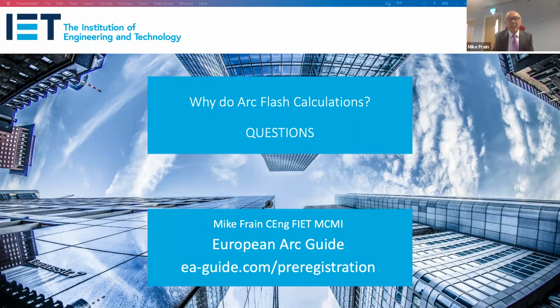Yes, I have. I hope that's not all you want to hear. I've worked for a major manufacturer and tester based in the south of England, and they wanted me to go in and look at their safe working system. So yes, we have a good handle on the electrical flashover - I was looking at shock risk as well down there. As I said earlier, the means to calculate the incident energy on systems like that is restricted to peer-reviewed papers, and that's what we used in that case to try to quantify the amount of incident energy.